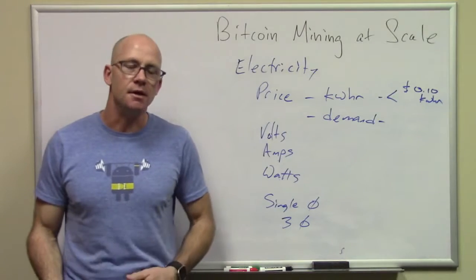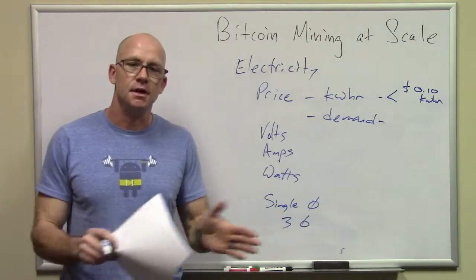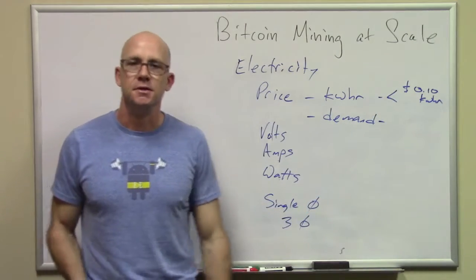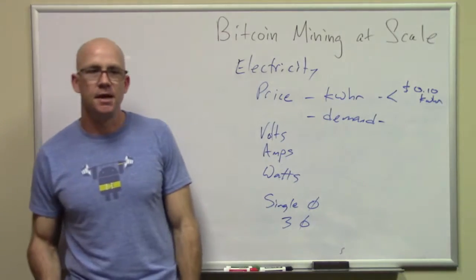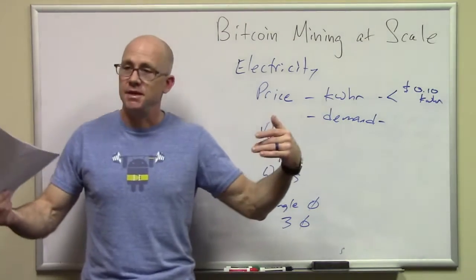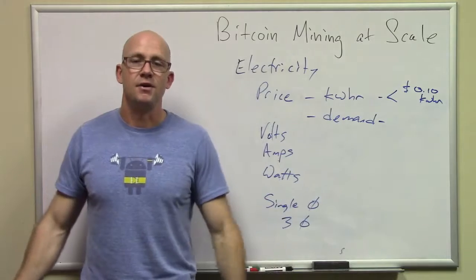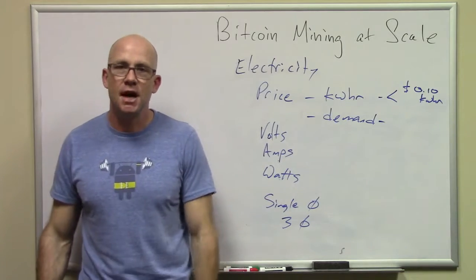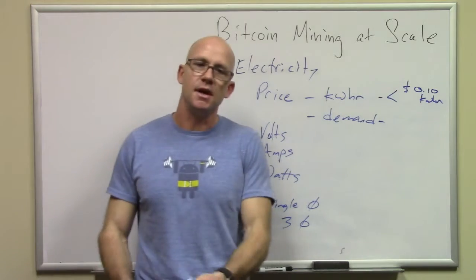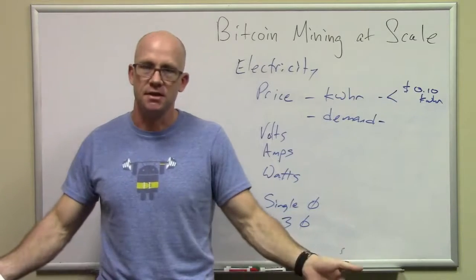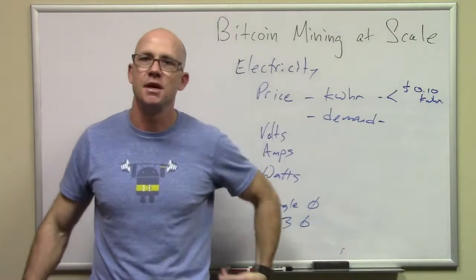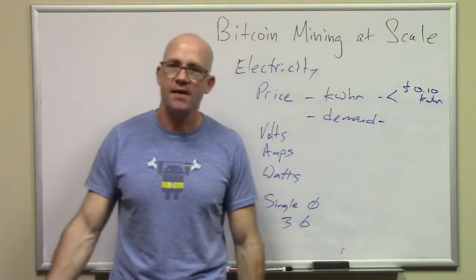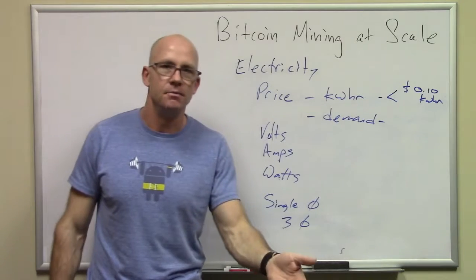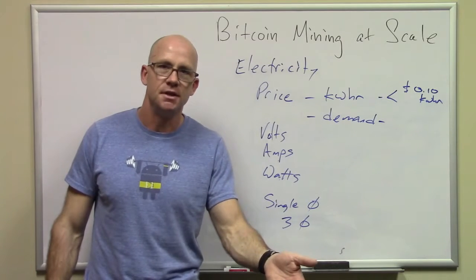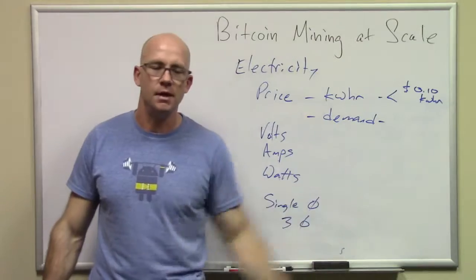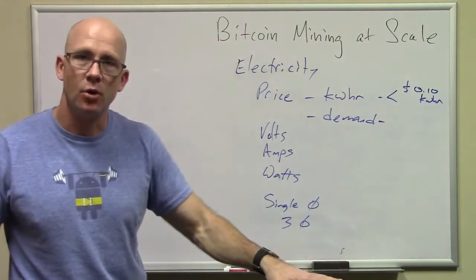Demand is a little trickier. Demand is variability in usage. So say you're an industrial plant where sometimes you need to have 500 kilowatts coming in, but most of the time you're using about 50. Well, you're going to have a huge demand variance because the electric company needs to bring in all the wires to handle 500 kilowatts, even though you're only mostly using 50, or 50 anyway. You're only using a portion of that.